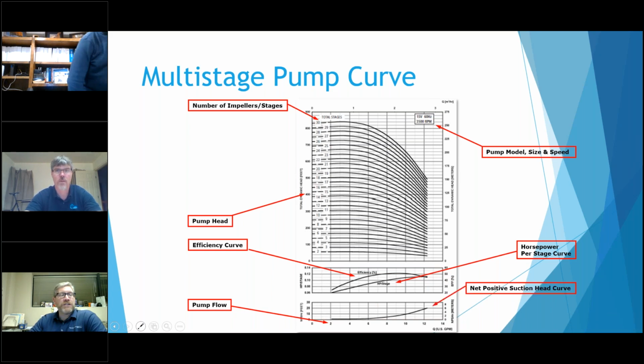And this is your net positive suction head. We touched on it a little bit earlier when we talked about open systems and closed systems. You can see here, this curve is pretty low at the beginning where you got a lower flow, and as it starts to jump up towards the end, if you're trying to get out towards this side of the curve, you can see if you run back over here, you might need 20 feet of pressure for that pump to work properly. So on those open systems, you've got to be careful where you're operating, so you have enough pressure at the pump suction for it to work. Like I said, you could get into a cavitation issue. Of course, that would end up destroying the pump. It'd certainly be pretty noisy and everything like that.